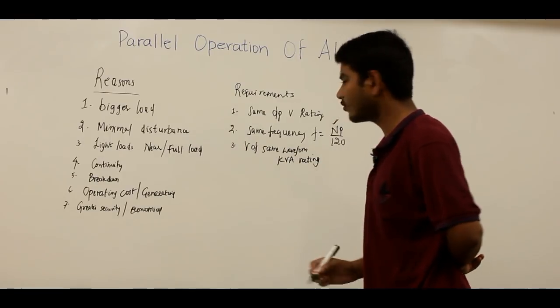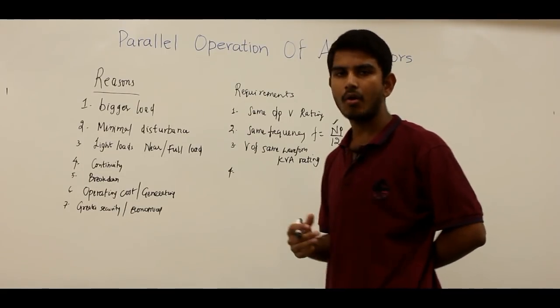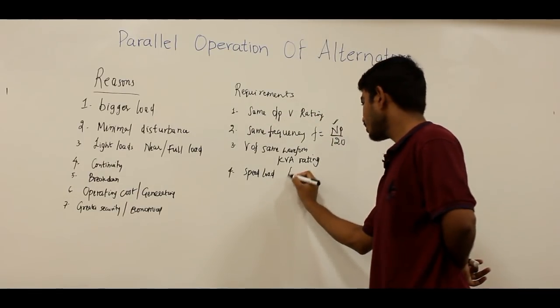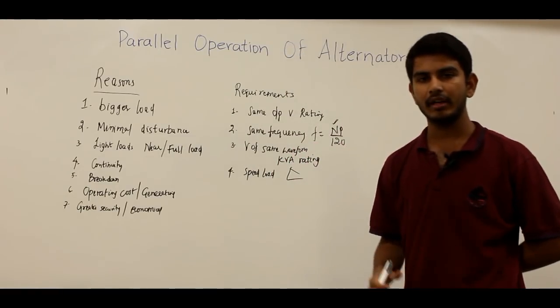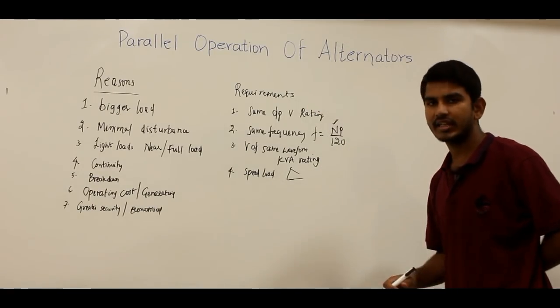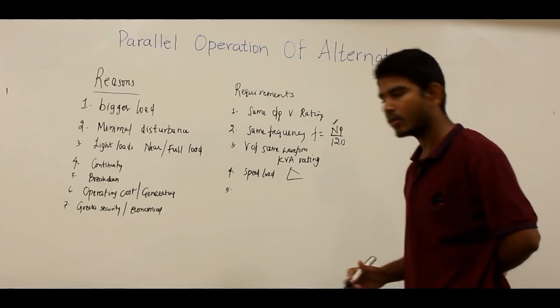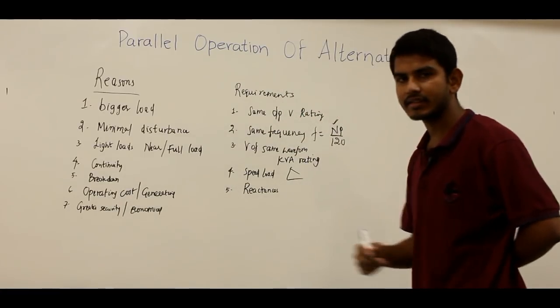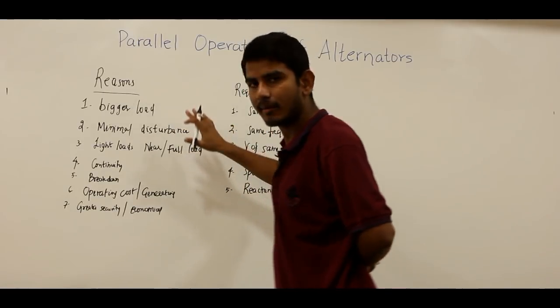The fourth requirement is that the prime movers of the two alternators should have the same speed-load characteristics, which is a drooping characteristic. This is required so as to load the generators in proportion to their output ratings. The fifth requirement is that the alternators going to be operated in parallel should have reactances in their armature; otherwise there won't be successful parallel operation.